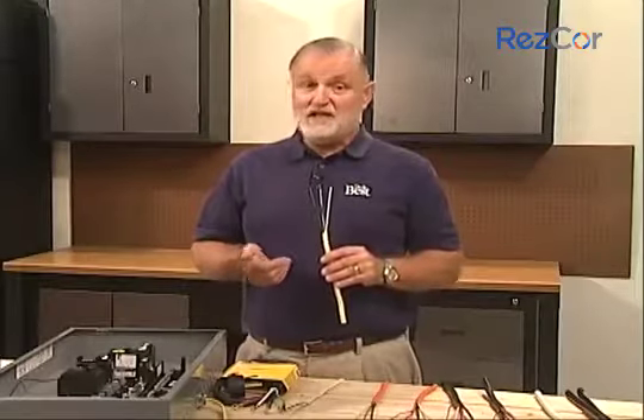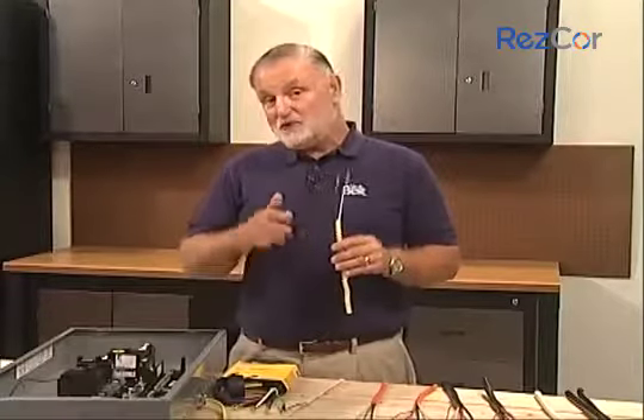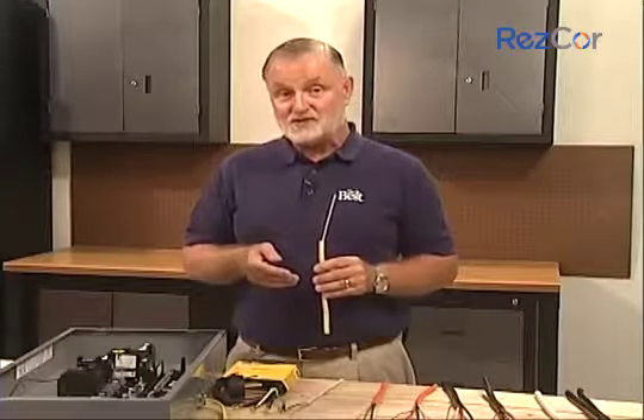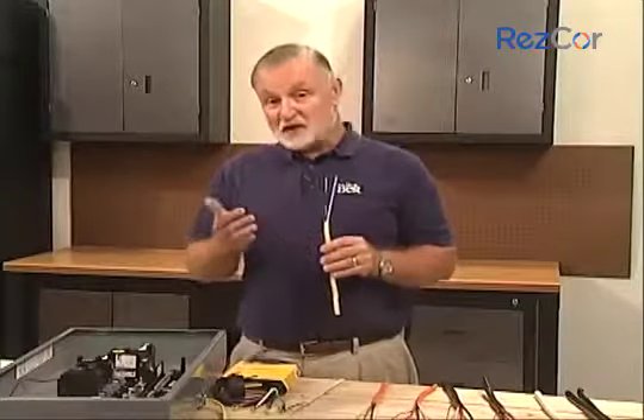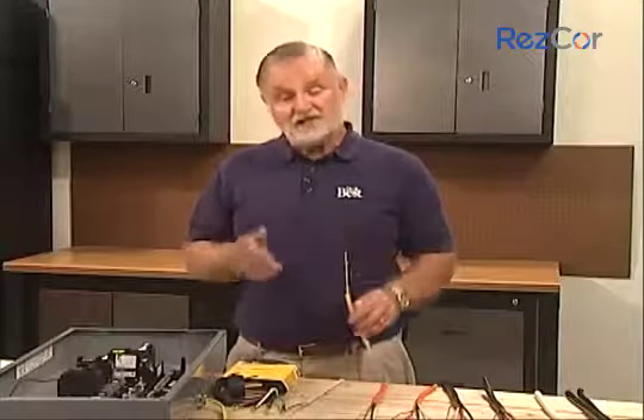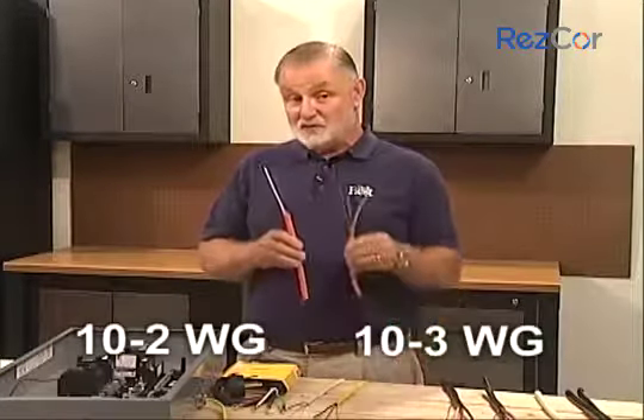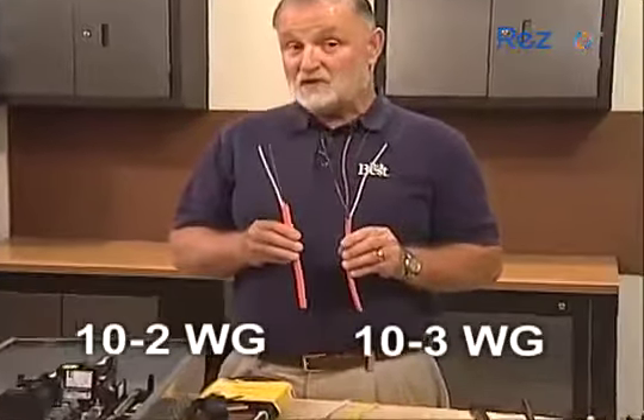This cable is specifically required as a minimum size for all bathroom circuits today, including the light fixture circuit. Other uses for this cable would be for small kitchen appliance circuits, refrigerators, built-in microwaves, and washing machines, just to name a few. The next larger cable is 10-gauge wire, sold as 10-2 with ground and 10-3 with ground. Both of these are orange.